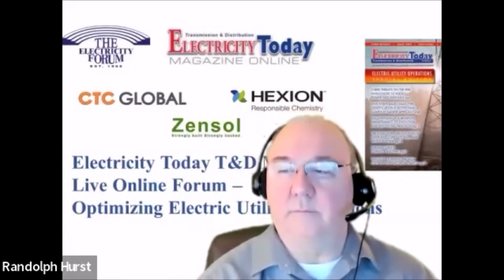Okay, and I will invite you to talk with our business development folks, who can help actually run some studies with you to demonstrate this. But in general, this is a smoother surface, so you get less turbulent flow. It's a lower sag, so you get less blowout as well. So you should see less galloping, certainly less sag, and we have tested for those that do have and want protection. There are some adders that you put onto that line, of course, to reduce or change the frequency of that. But you can imagine that with that lower sag, you're going to have less opportunity for galloping. It's the smooth surface, and you have less blowout.